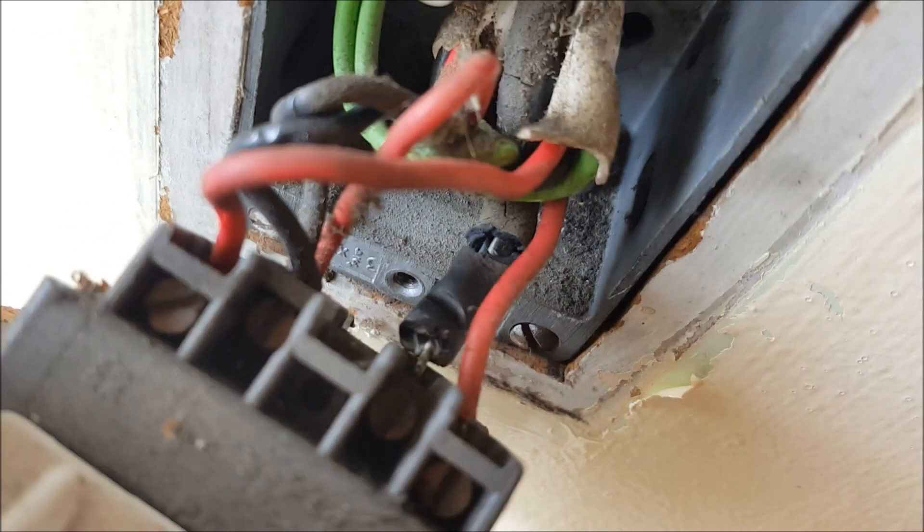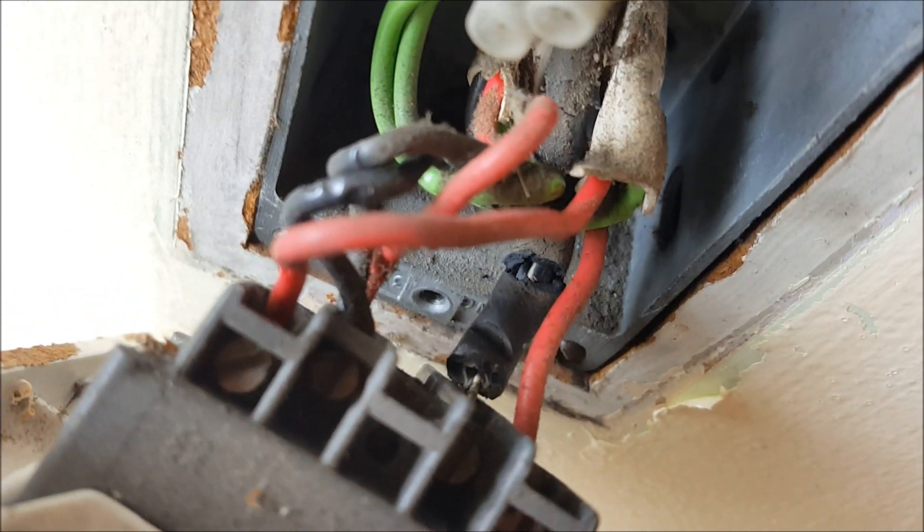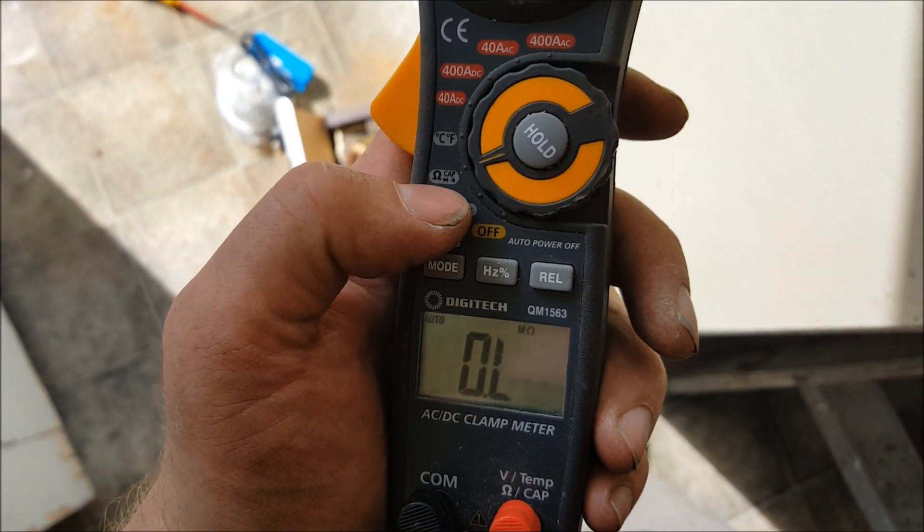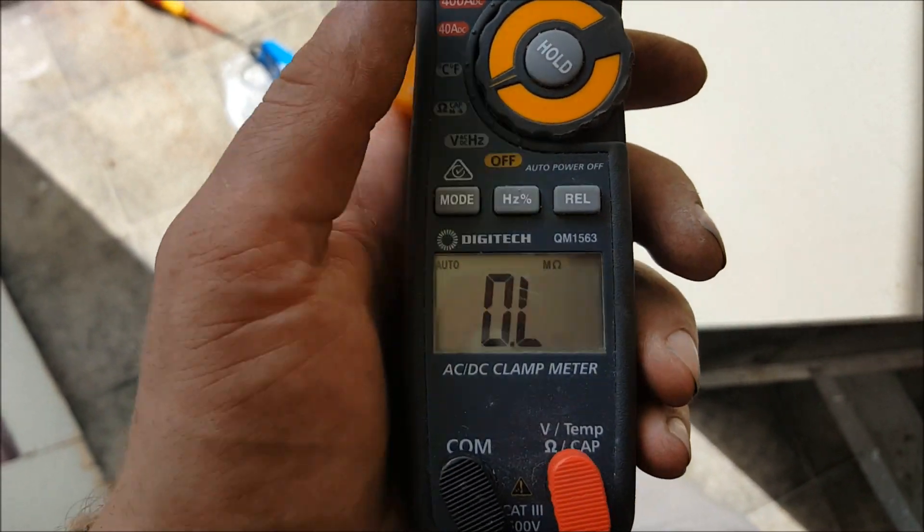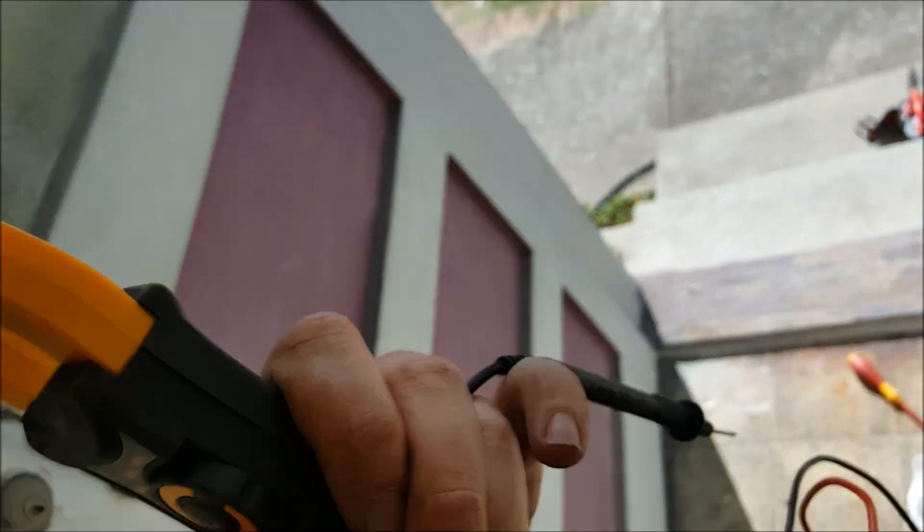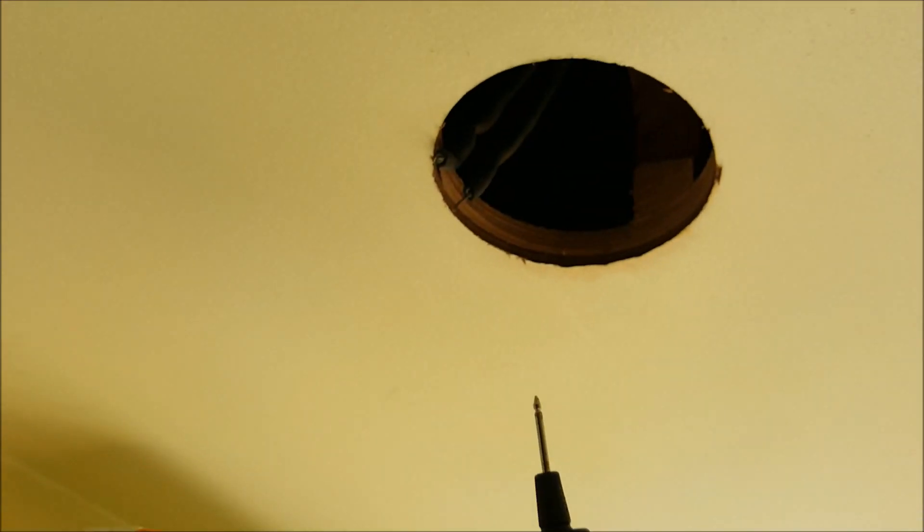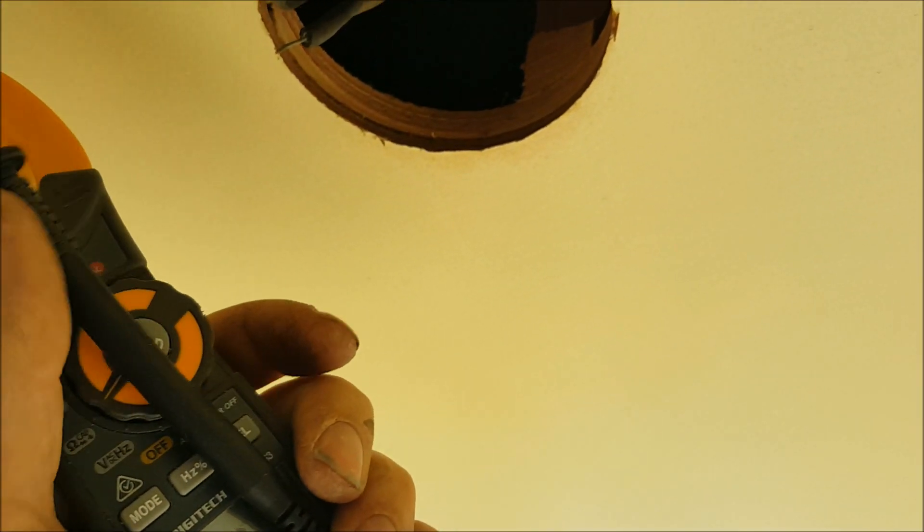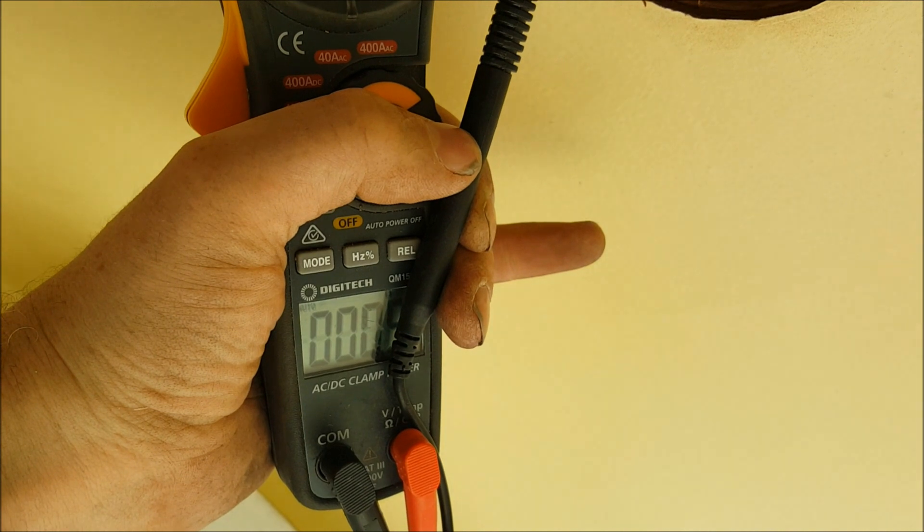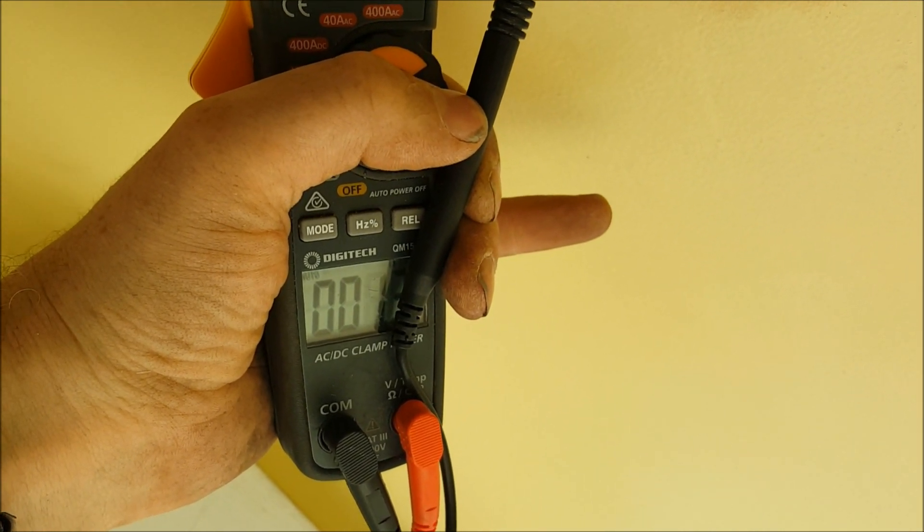Where the phase with that switch wire there, the one that's starting to fall apart down the bottom there, that rubber one, we'll put our meter onto ohms. Throw a meter onto ohms, that symbol there, and then we'll just test between that one and one of the cable cores. There we go, zero ohms. That's what we're looking for. That cable there is our phase.